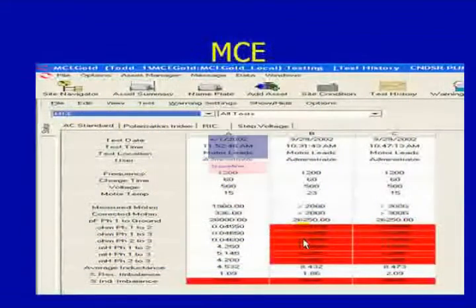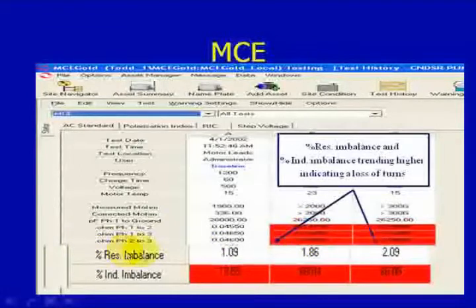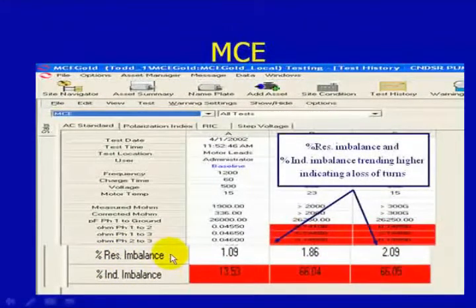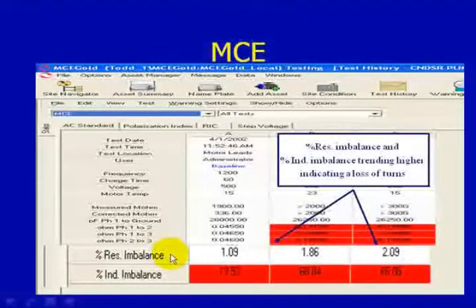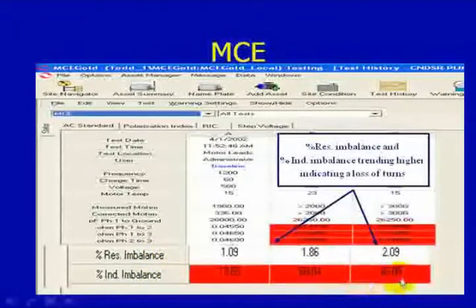So how would we analyze a stator fault with our MCE technology? As we see here, we're looking at our resistive imbalance and our inductive imbalance. These are important because if we change resistance in one of the phases, that will create a resistive imbalance, potentially current imbalance, and excess heat. Inductive imbalance works the same way — as we lose turns in one of the phases, that will change the inductance measurement, and that will create a higher inductive imbalance, causing this number to go into the red and increase as you lose turns.